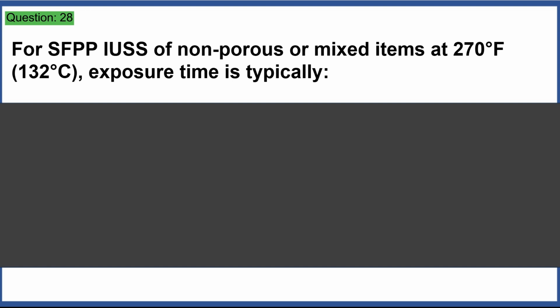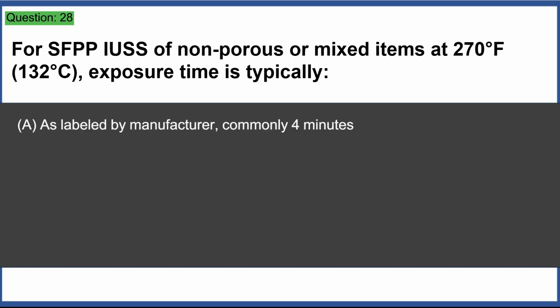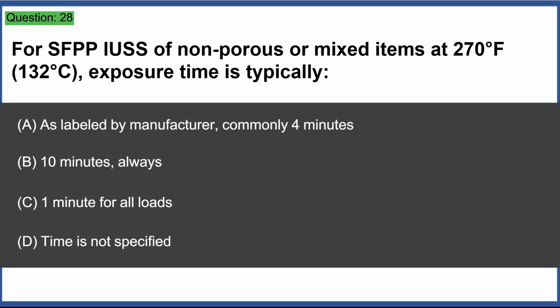For SFPP IUSS of non-porous or mixed items at 270 degrees Fahrenheit, 132 degrees Celsius, exposure time is typically: A. As labeled by manufacturer, commonly 4 minutes. B. 10 minutes, always. C. 1 minute for all loads. D. Time is not specified. Answer: A. As labeled by manufacturer, commonly 4 minutes.